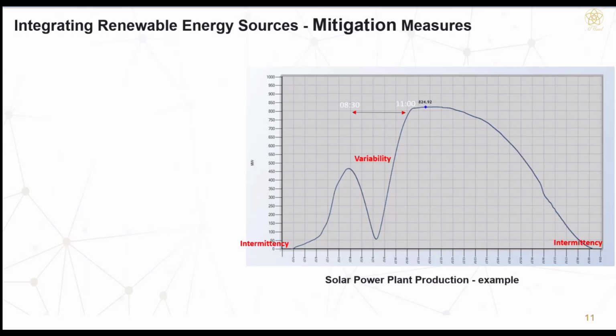The problem is mainly with variability. Here I'm showing an extreme scenario of one PV power plant we have here in the region, the GCC—an extreme scenario of a solar eclipse, where around 450 megawatts dropped within almost half an hour because of the eclipse, then between 8:30 and 11 it recovered to its full declared capability.